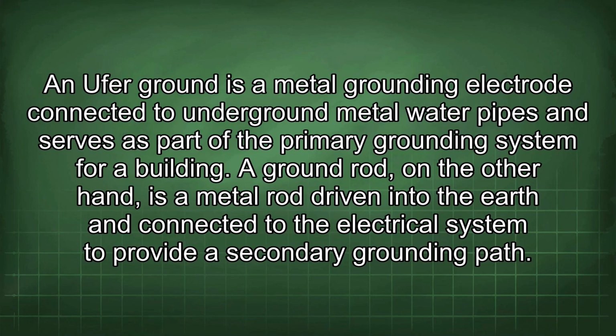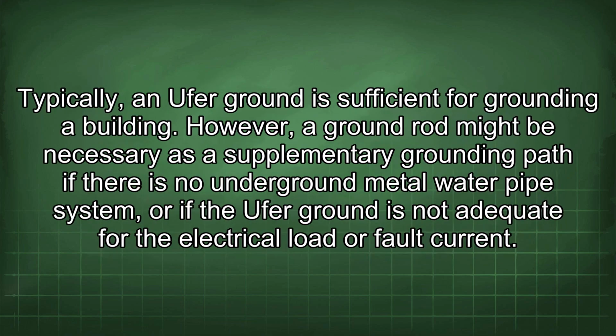An Ufer ground is a metal grounding electrode connected to underground metal water pipes and serves as part of the primary grounding system for a building. A ground rod, on the other hand, is a metal rod driven into the earth and connected to the electrical system to provide a secondary grounding path. Typically, an Ufer ground is sufficient for grounding a building.